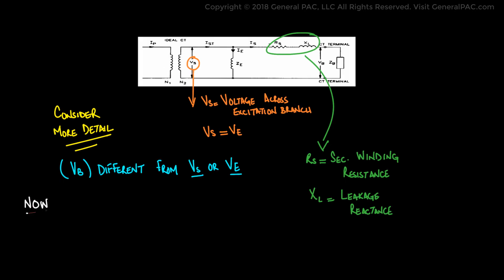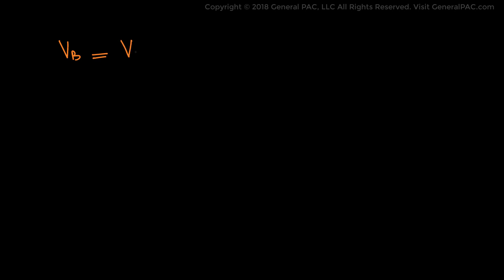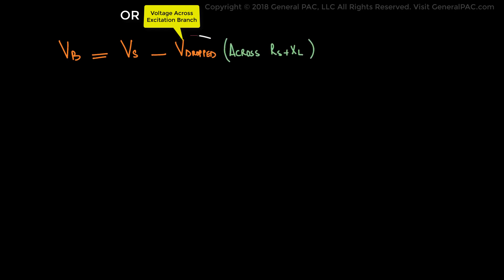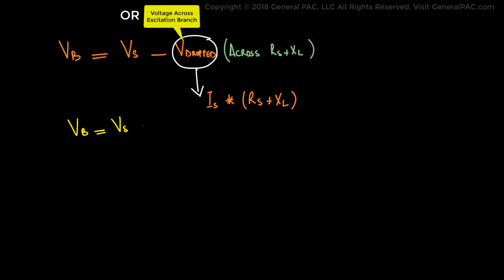The way we calculate it: if we wanted to calculate the voltage across the burden, that simply equals the secondary winding voltage Vs minus the voltage drop across RS plus XL — which is the current going through RS and XL times the impedance of RS plus XL. So that is represented by the equation that you see.